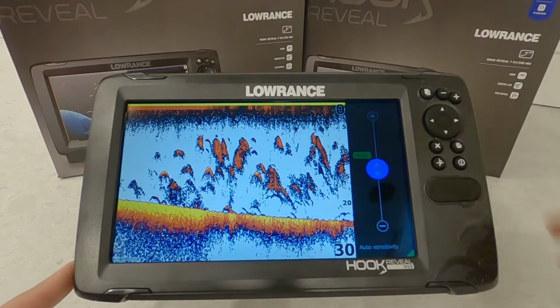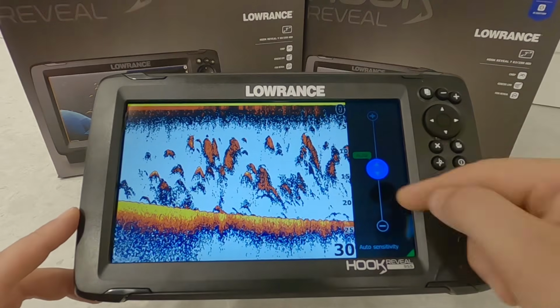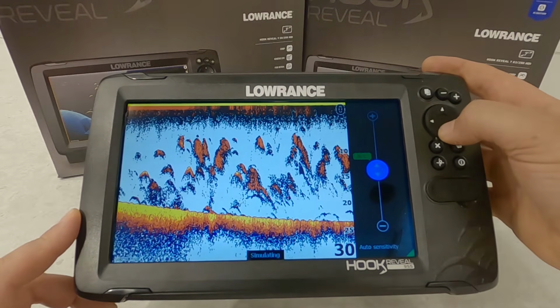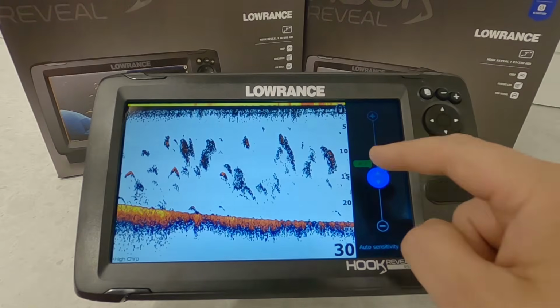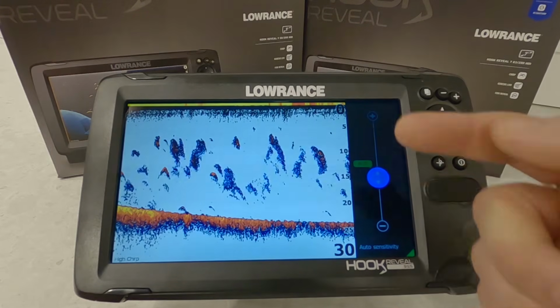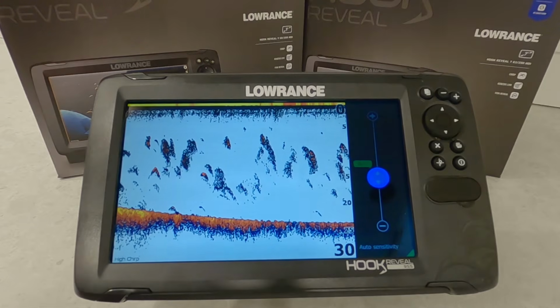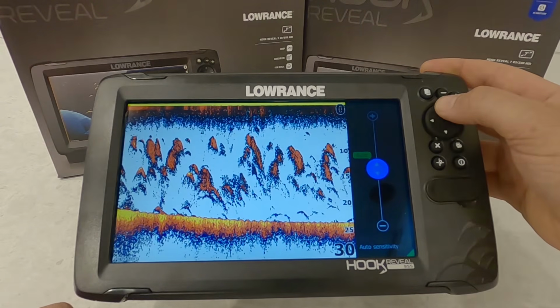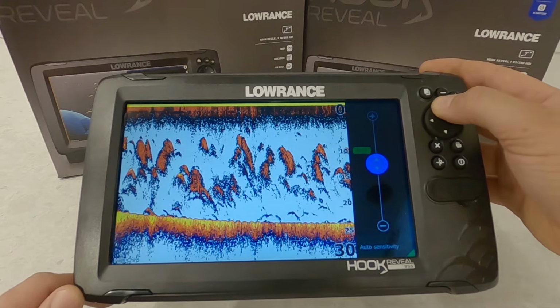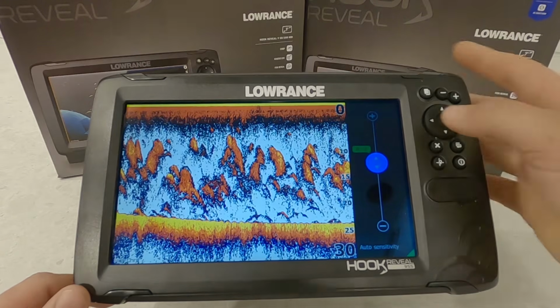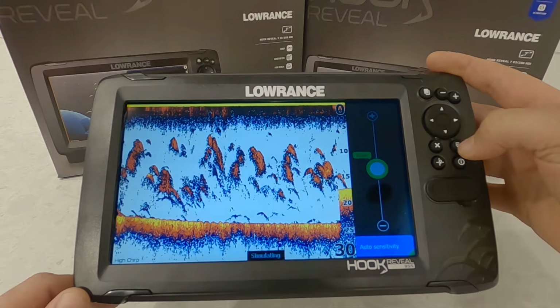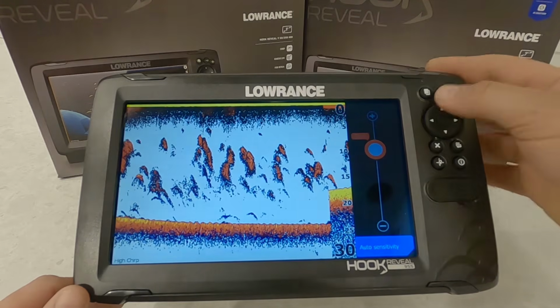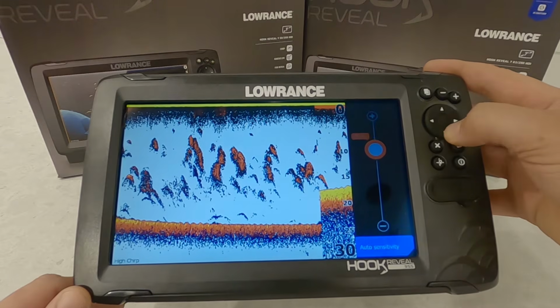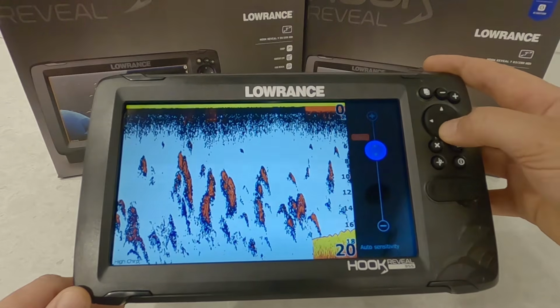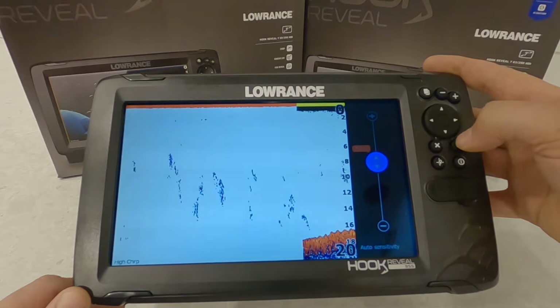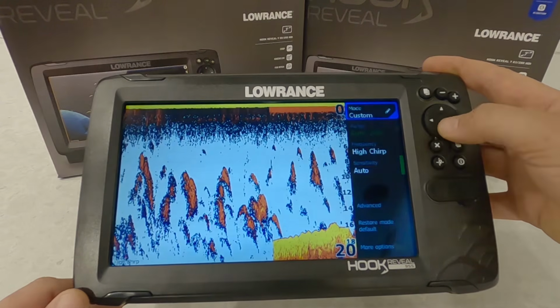Now our sensitivity, again, that is set to auto, so we can leave that in auto, but if we're finding it's showing too much information, we can drop it down. It's still going to remain in auto, but it's going to do -7% to what the automatic mode thinks it needs. So now we're at 0, the auto is doing it all on its own. If we want to see more information than the auto is showing us, we can turn that up as well. Then if we want to turn auto completely off, we can hit enter, come down here, and now we're manually in control of our sensitivity. You just toggle between the two, hit enter on the one you want to adjust, and then you can put that wherever you like. Again, I'm going to leave auto on in this case.